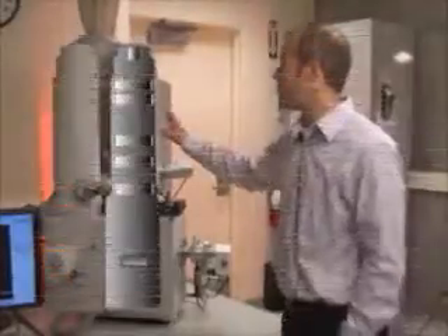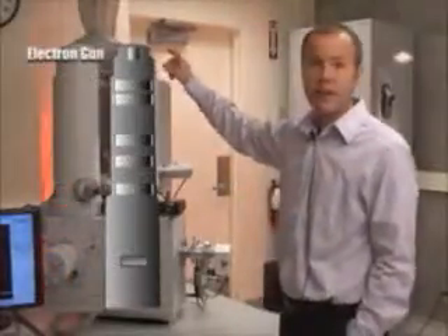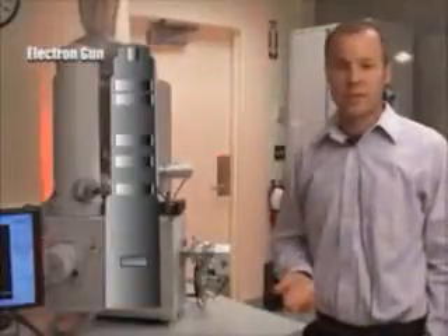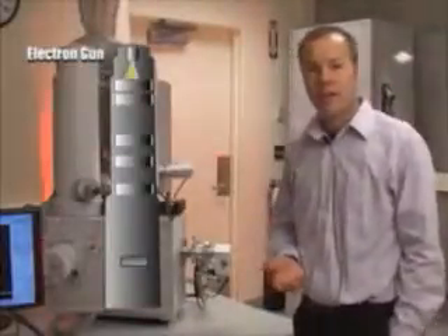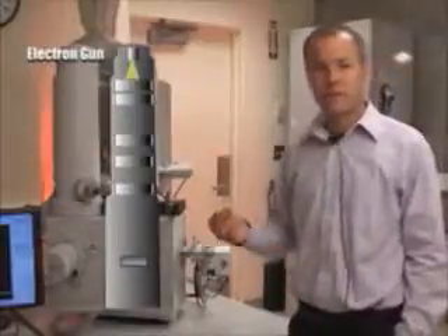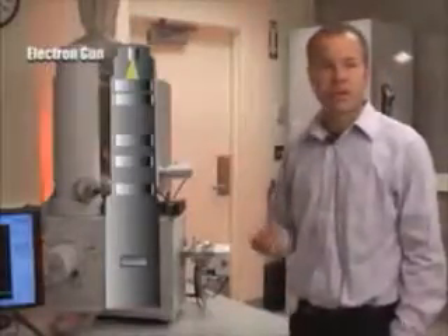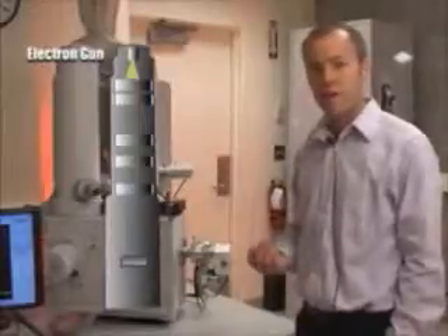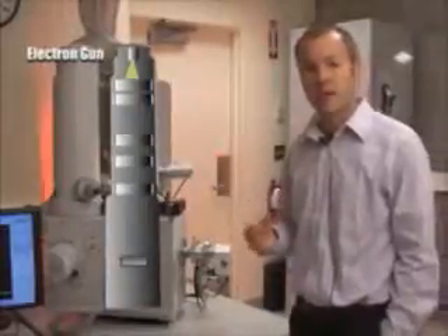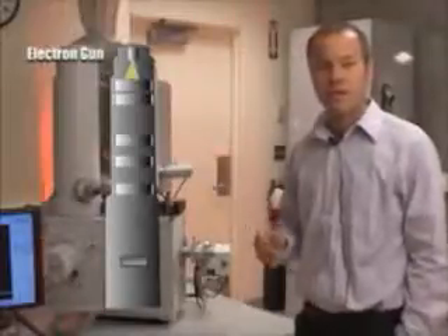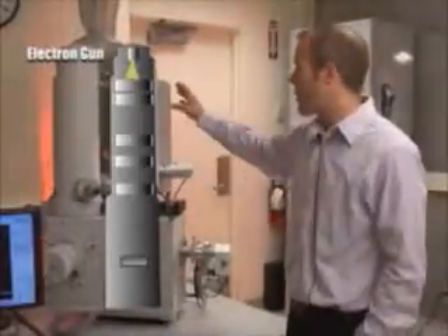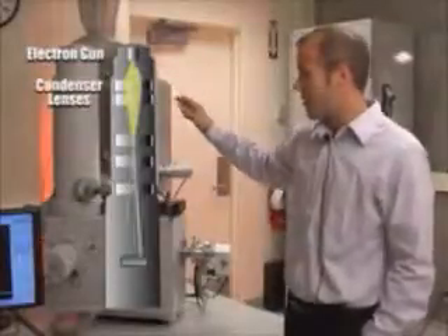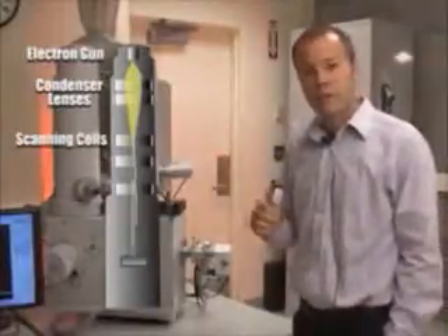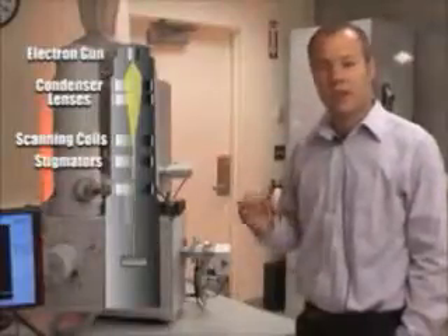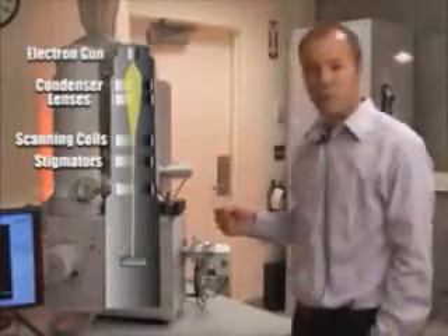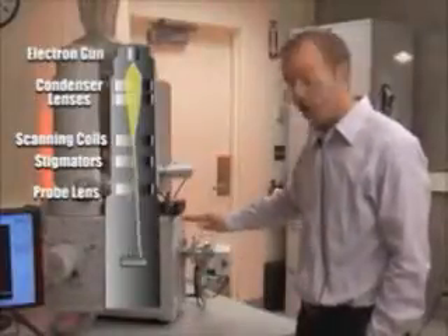At the top of the column, in this section right here, is an electron gun. As I mentioned, this is a field emission scanning electron microscope. So the electron gun is essentially a tungsten filament, a very sharp filament. We use a strong electric field to draw a current off of that filament, and that creates the probe beam that you use to impinge on the sample and image the sample. Below the electron gun, there are condenser lenses, scanning coils for moving the beam, stigmators for adjusting the roundness of the beam, and ultimately there's a probe lens at the bottom, down at about this level.